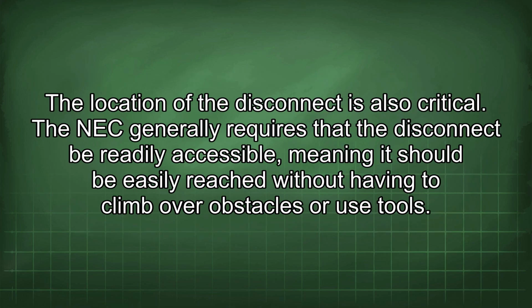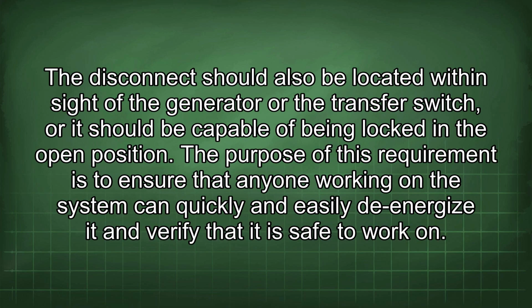The location of the disconnect is also critical. The NEC generally requires that the disconnect be readily accessible, meaning it should be easily reached without having to climb over obstacles or use tools. The disconnect should also be located within sight of the generator or the transfer switch, or it should be capable of being locked in the open position. The purpose of this requirement is to ensure that anyone working on the system can quickly and easily de-energize it and verify that it is safe to work on.